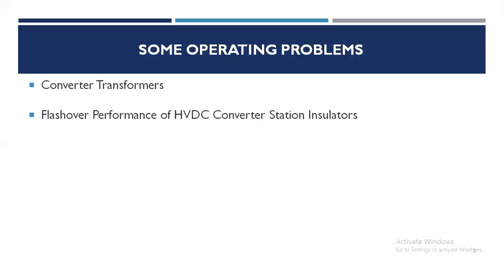The application of booster sheds, silicone grease coating, RTV silicone rubber coating, etc. has resulted in reducing the flashovers per converter station by a factor of 10, to about 0.1 per station per year. Recently, dry type bushings with SF6 insulation have been developed, which are also safer from fire risks.